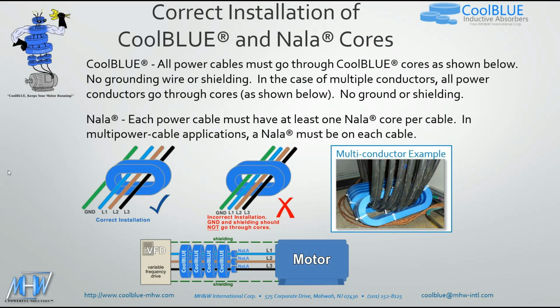So again, this is doing some reiteration here. So the correct installation of CoolBLUE and NALA cores. CoolBLUE, all power cables must go through the CoolBLUE as shown below. No grounding wire or shielding. In the case of multiple conductors, all power conductors go through the cores as shown here. This looks like there's, I think it's 3 cables per phase. And then the NALA, you must have at least 1 cable per phase on each cable. This picture doesn't show the NALAs, but then you would actually have a NALA here, and a NALA here if this is 3, 3, and 3.